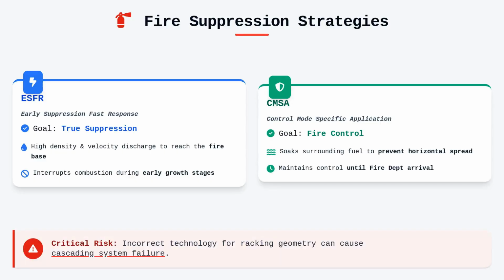Choosing the wrong technology for the specific racking geometry can lead to cascading system failure, where the heat output overwhelms the water discharge capacity. You must ensure that the piping network and the available water supply are sufficient to meet the specific discharge requirements for the chosen technology at the most remote area of the rack.